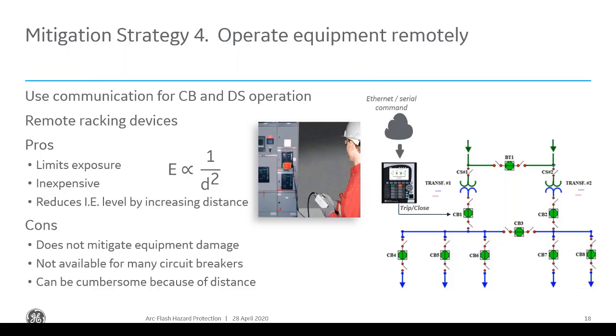They can be cumbersome because you have to walk around with that lead and that switch, and then you have to plug it in. Sometimes it's removable. So the act of just plugging in, you're still in front of the switchgear.